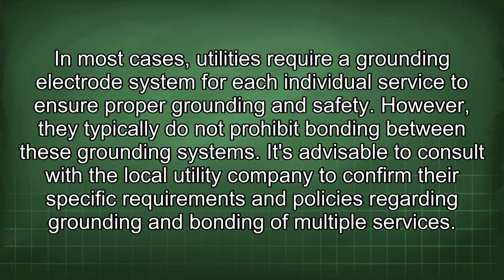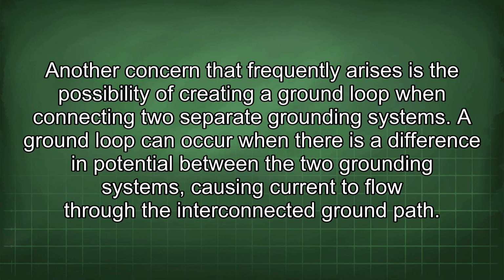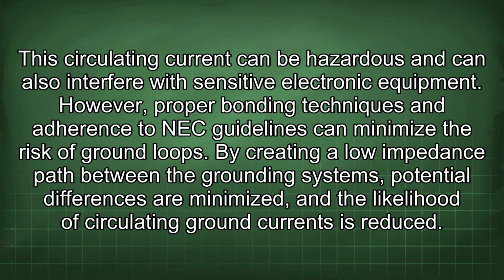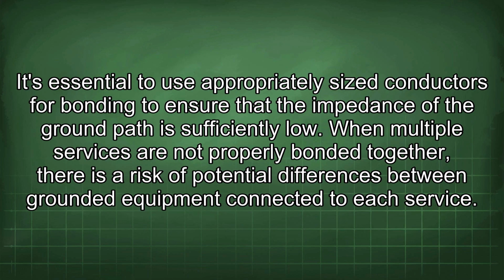of multiple services. Another concern that frequently arises is the possibility of creating a ground loop when connecting two separate grounding systems. A ground loop can occur when there is a difference in potential between the two grounding systems, causing current to flow through the interconnected ground path. This circulating current can be hazardous and can also interfere with sensitive electronic equipment. However, proper bonding techniques and adherence to NEC guidelines can minimize the risk of ground loops. By creating a low impedance path between the grounding systems, potential differences are minimized and the likelihood of circulating ground currents is reduced.